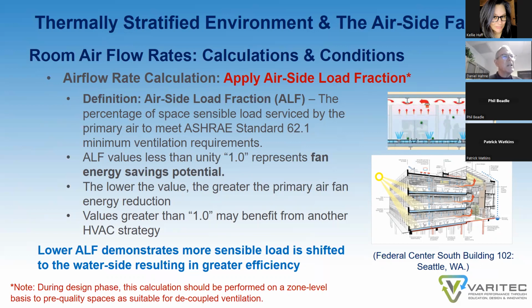That is the amount of sensible energy removed from the space by bringing in the supply air temperature at 62 to 65 degrees through a displacement diffuser and assigning how much sensible load is met with that air side. Once that is determined, you can then begin to size the radiant component. How many square feet of radiant panel or active radiant panel or active sail are required to satisfactorily meet the remaining sensible load. Lower airside load fractions demonstrate and argue for a more effective use of passive radiant technologies.